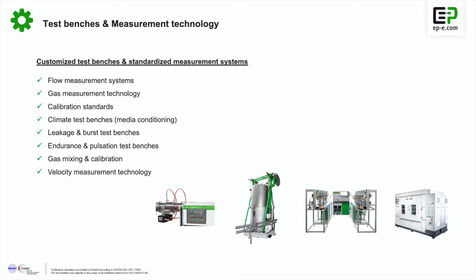The second from the left is our airflow measurement bell - the bell prover, the most precise device for airflow calibration. This is needed for governments and national standards. Think of it like the kilogram or the meter: for the meter, you have a certain length that serves as the master reference for determining what a meter is. The bell prover works the same way.